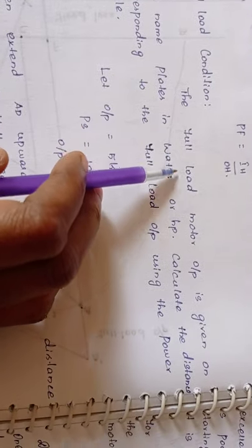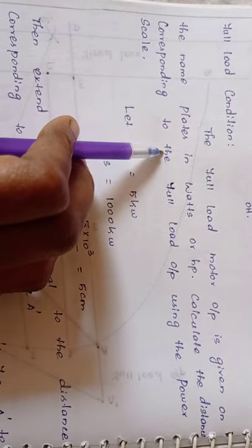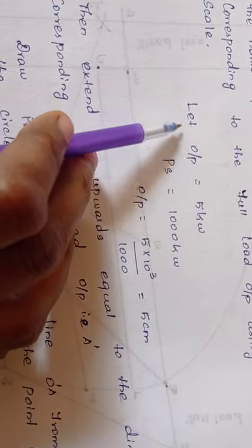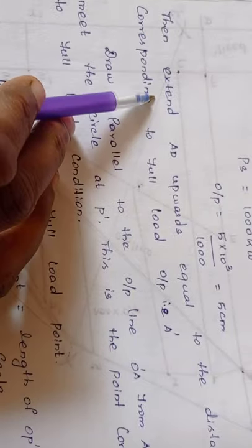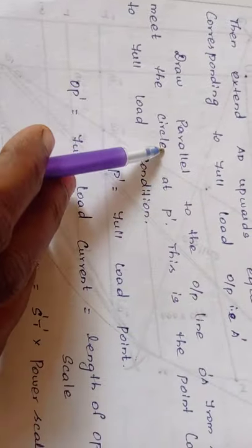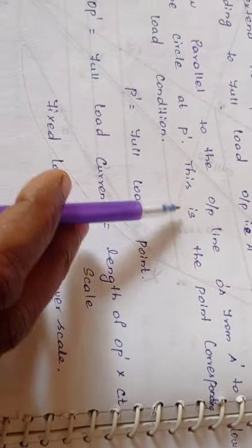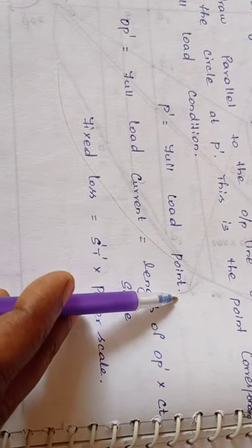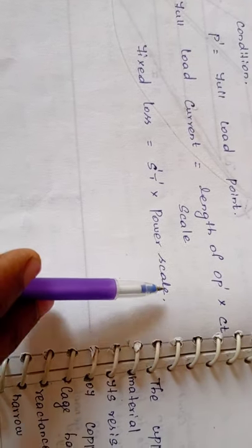For full load condition: the full load motor output is given on the nameplate in watts or HP. Calculate the distance corresponding to full load output using the power scale. For example, if output = 5 kW and PS = 1000 W/cm, then output distance = 5000/1000 = 5 cm. Extend AD upward by this distance to point A-dash, then draw a line parallel to the output line O-dash A from A-dash to meet the circle at P-dash, which is the full load point. OP-dash = full load current = length of OP-dash × current scale. Fixed loss = S-dash T-dash × power scale.